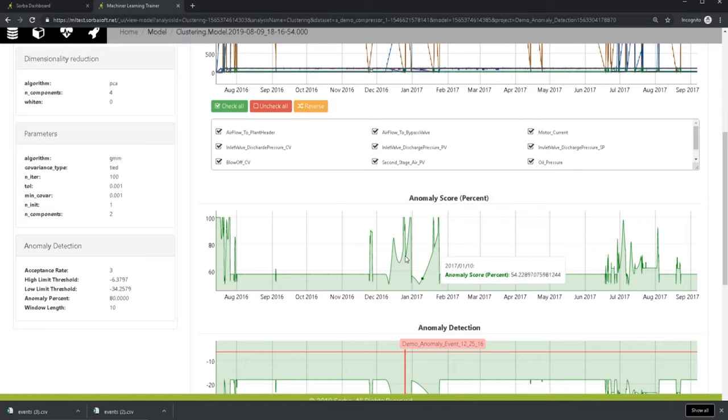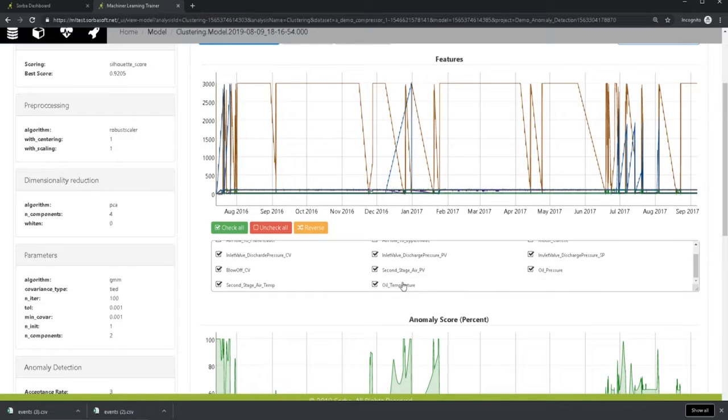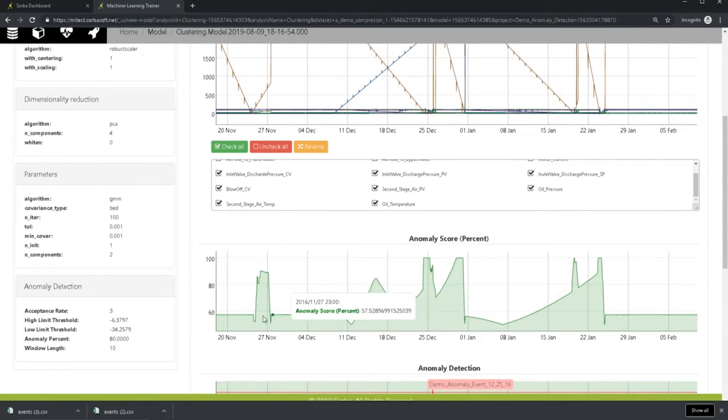So what we're going to do for an example is that I'm going to zoom in. Let me make sure synchronization is still there. I'm going to zoom in on this specific issue. And then we see that maybe we had a failure event that is its own individual or independent failure event. We come in and we see that, okay, now there is some type of degradation between December 11th and December 18th. It peaks. Maybe there was a preventative maintenance event that helped slow down the curve, but you can see it came right back up and then shot up.